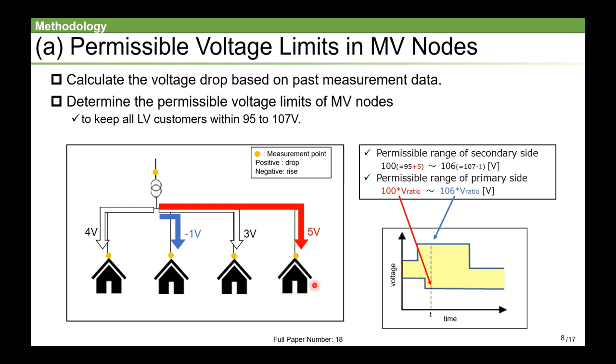Here, in step A, the permissible voltage range of MV nodes is determined. First, the voltage drop is calculated from the measurement voltage on the primary side of the pole transformer and each LV consumer. Then, the permissible voltage range of the primary side is determined so that all LV consumers' voltage can be within 95 to 107V.